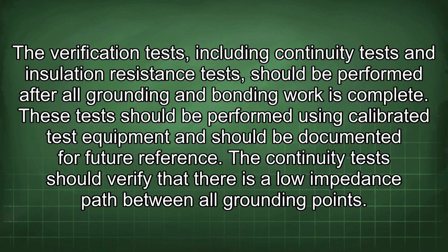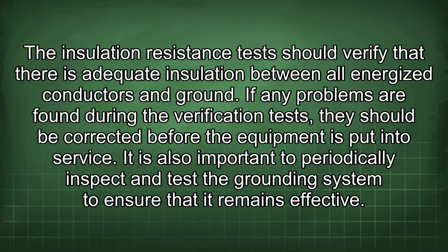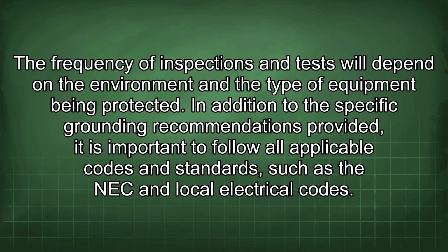The continuity test should verify that there is a low impedance path between all grounding points. The insulation resistance test should verify that there is adequate insulation between all energized conductors and ground. If any problems are found during the verification tests, they should be corrected before the equipment is put into service. It is also important to periodically inspect and test the grounding system to ensure that it remains effective. The frequency of inspections and tests will depend on the environment and the type of equipment being protected.